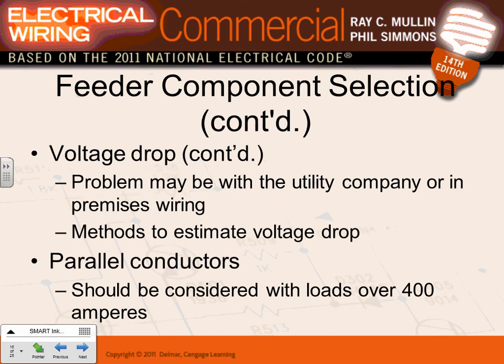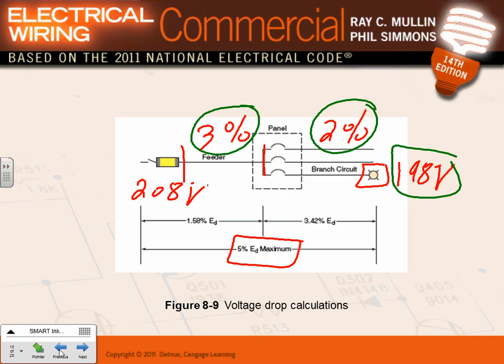So if you have a problem with the voltage drop, one question would be to check with the utilities. So here you go. Andrew, my friend, if you go back here, this voltage is coming from Excel. You have to go measure the voltage at the service. Excel might have given you 200, right? If you start with 200, what do you think you're going to end up with here? Much lower. So your start point is the utility.